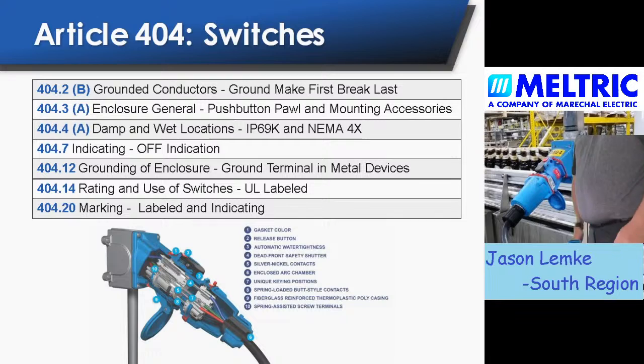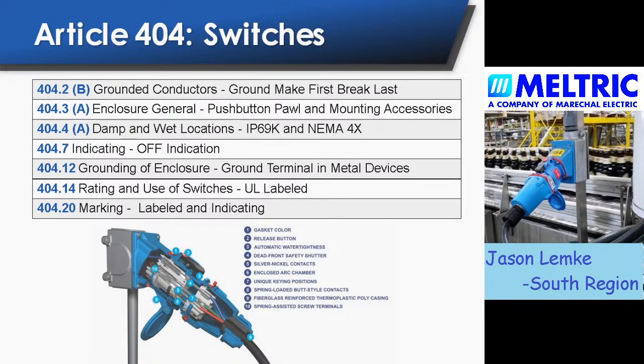So I'm going to show you some of the things that we do in our device that actually make us a switch. So I'm going to transition over to this. And what you'll see here are some of the key pieces of a Meltric device that allow us to meet the requirements of an Article 404 switch. So a couple of those things are we are able to have the grounded conductor make first and break last. We have the enclosed push button capability, so that's what that button is there for. When the plug is removed from the receptacle, you can see that we have an off indicator on it, or maybe you can see it. It's a little difficult to do it with the background.